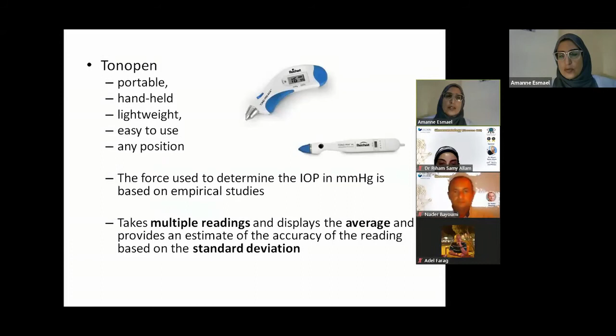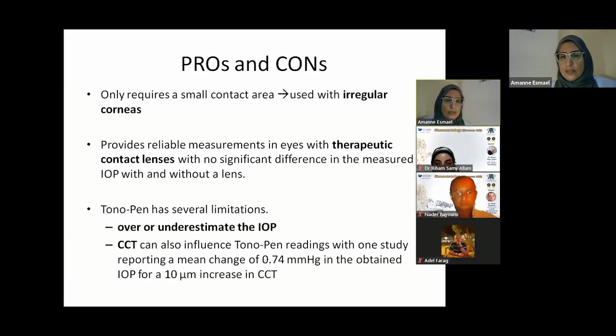However, it only requires a small contact area, so it is very useful in people with an irregular corneal surface, and it provides reliable measurements in situations like wearing therapeutic contact lenses. Studies have shown that the difference in intraocular pressure measured with or without the therapeutic contact lens is quite slight. The Tonopen limitations include that it over- and underestimates intraocular pressure in correlation to GAT, and just like GAT, central corneal thickness does have an impact on it. However, studies have shown that this impact is around 0.74 millimeters mercury for each 10 microns.